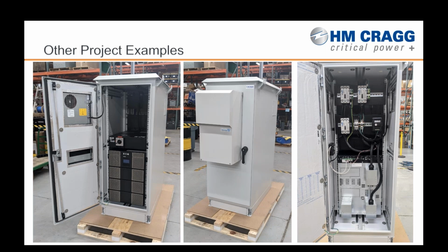What I find really cool is the picture on the far right, which shows how we approach each system design in the build-out, including all the power distribution, overcurrent protection in the circuit breakers, and all the wiring completed in our factories. The customer end user gets a single input, single output breaker in this design, along with UPS input, HVAC system, hydrogen sensing, lighting, and signaling — all accessories and devices included are pre-wired, powered up, tested, set points set, and everything verified before it ships.